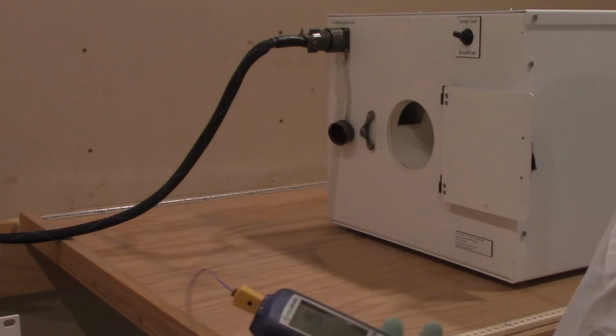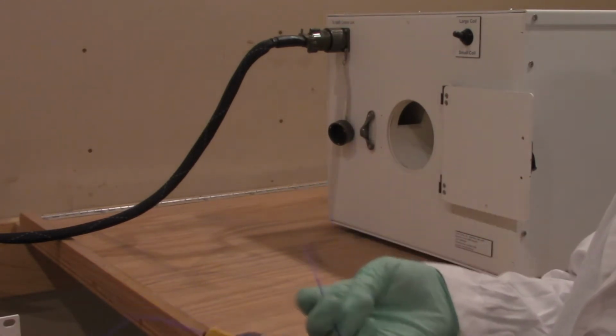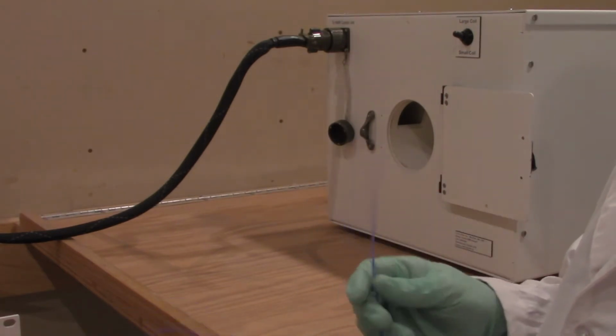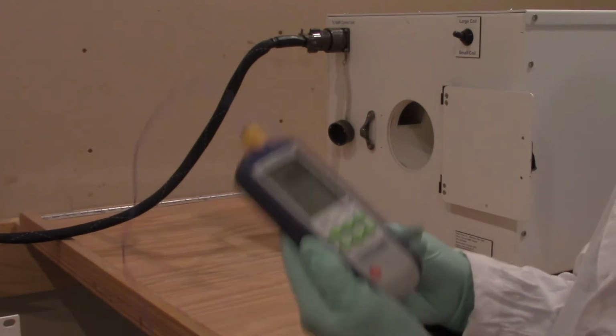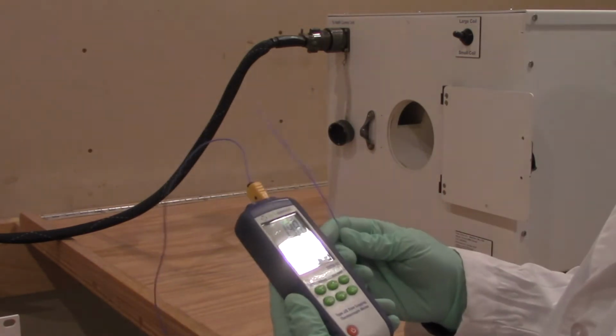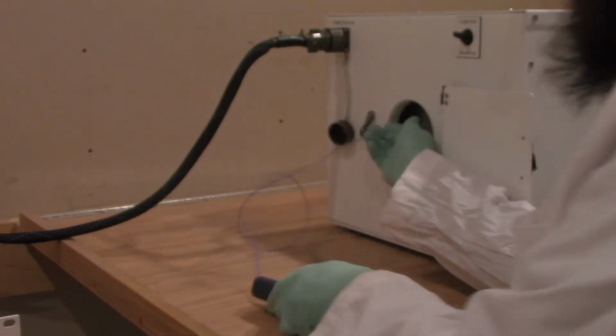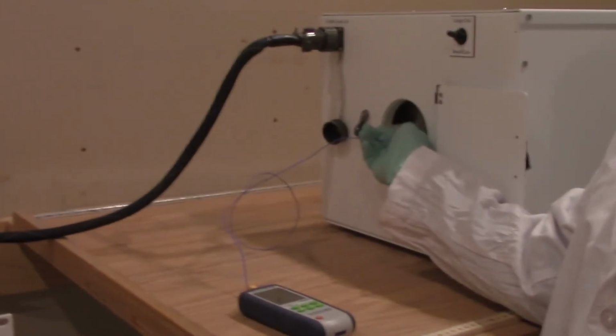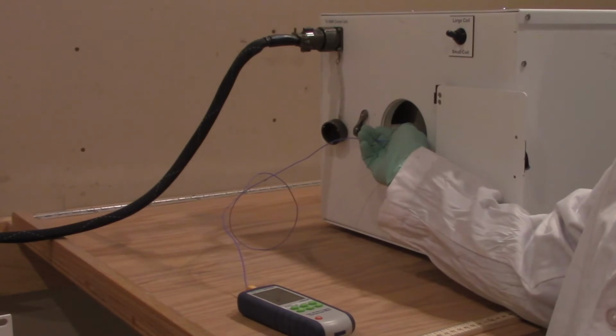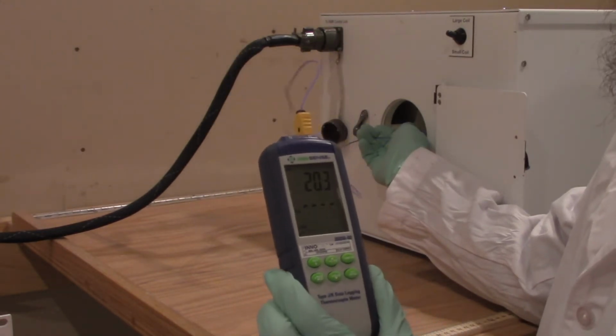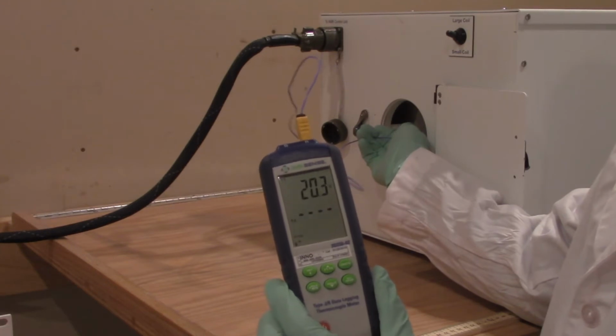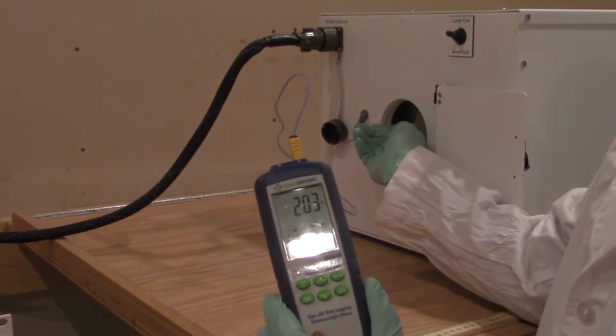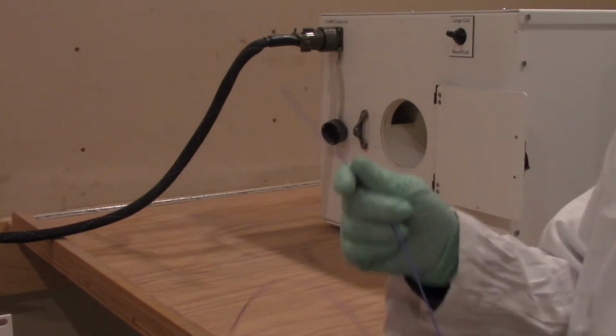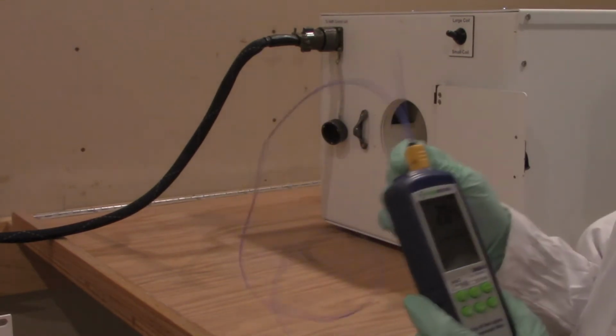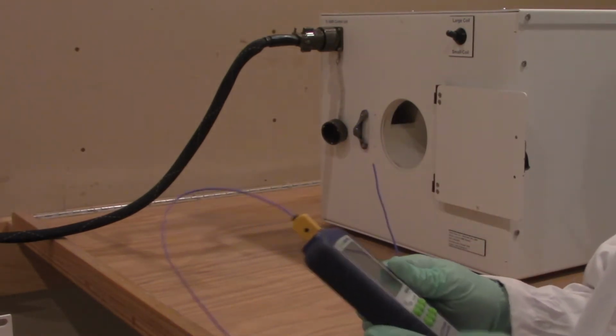And finally, the temperature is important to be constant, like we said, and we want to measure what that temperature is and record that so we know what the temperature of the sample is when we go to data processing. You can use any sensor you want, but I'm just using the simple thermocouple sensor, and we'll put the probe into the tube and get a reading. Right now you can see it's stabilized right around 20.3 degrees. So we'll record that and use that later on. Of course, we don't want anything metal inside the NMR instrument, so we can't leave this temp sensor in here.